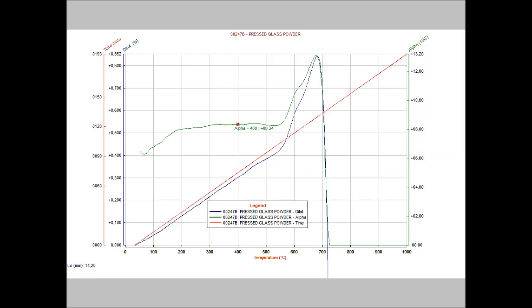Another quite interesting point for technicians who make daily use of the dilatometer is that there is no danger of spoiling the measuring system when the sample melts on the holding plate. The fact that the measurement is carried out with lower resolution compared with the traditional dilatometer is largely compensated by the fact that the measurement is absolute and it does not depend on the calibration curve.